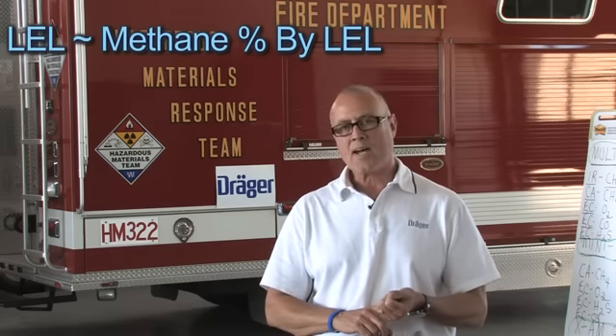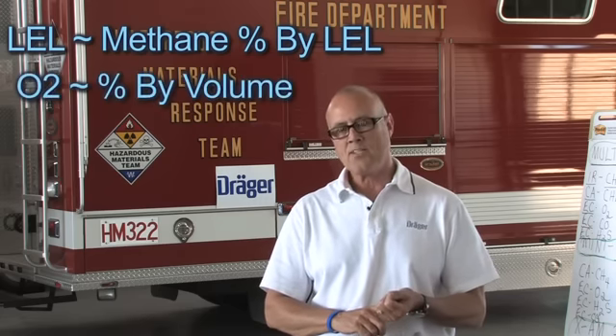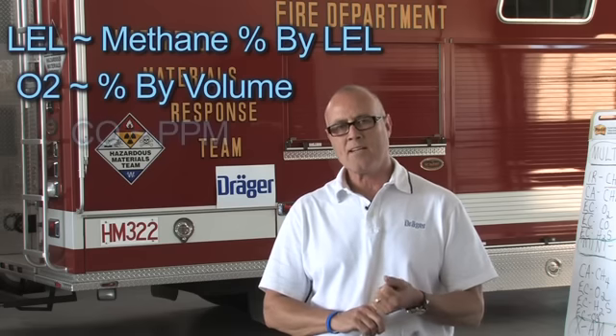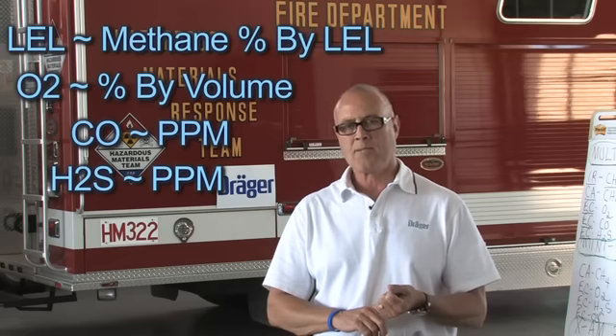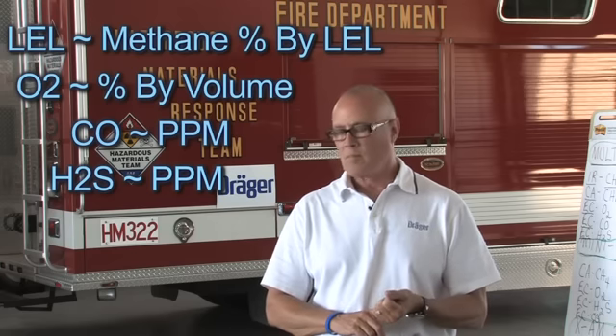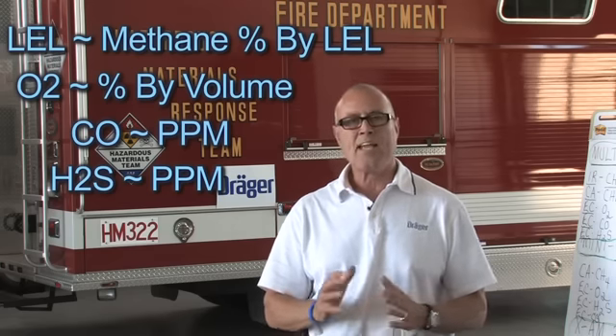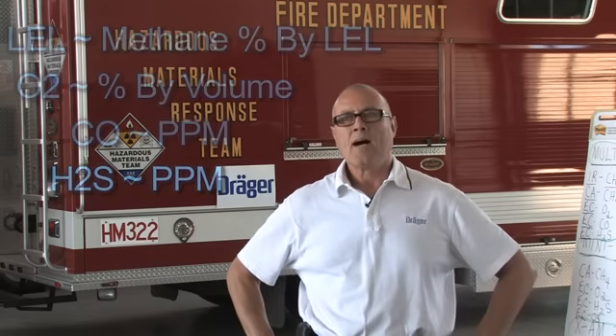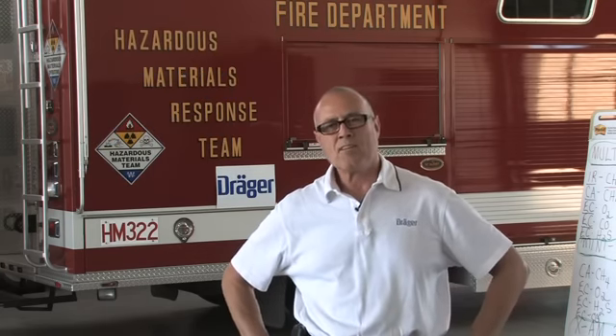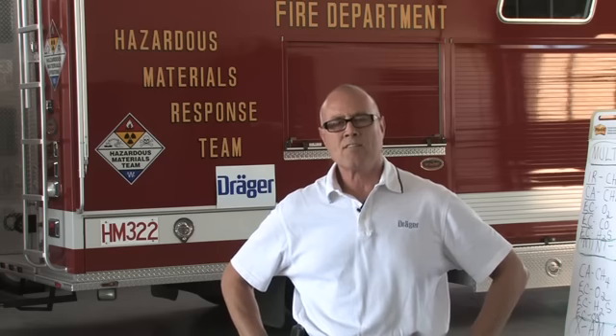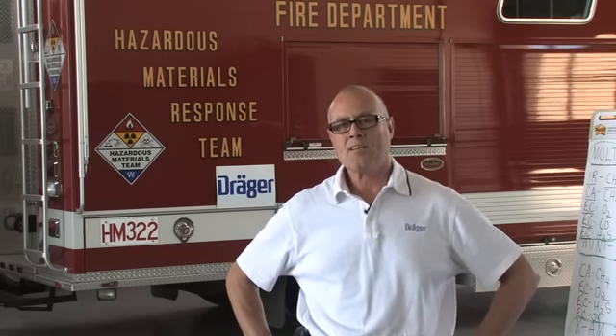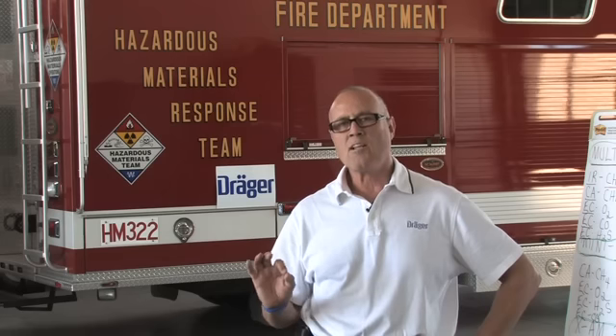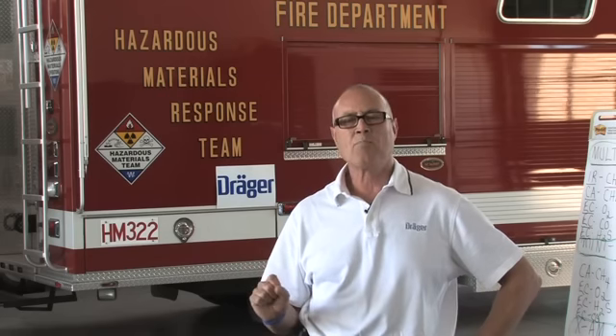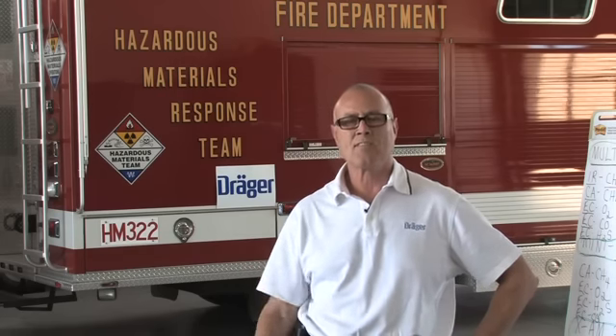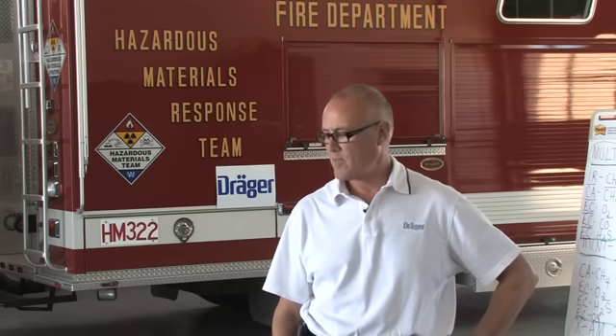They monitor for oxygen in the percent by volume range, carbon monoxide in the parts per million range, and hydrogen sulfide in the parts per million range. CO, carbon monoxide, and H2S, hydrogen sulfide, are both toxic at very, very low concentrations. So the idea is to protect the firefighters from the very low, minute toxicity exposure of carbon monoxide and hydrogen sulfide. And that is the goal of these instruments.